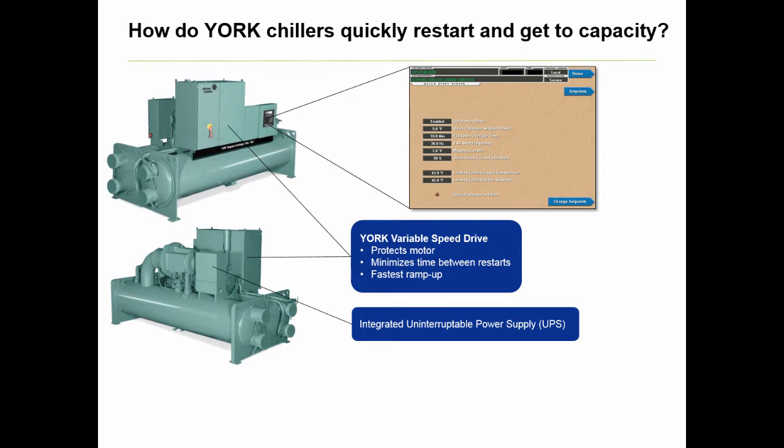Third, most YMC-squared models have an integrated uninterruptible power supply, or UPS, that provides smart power management to keep the magnetic bearing controller, OptiView panel, and OptiSpeed VSD energized until the facility's emergency generator is activated.